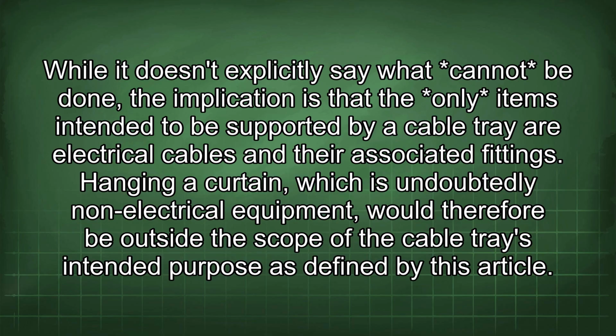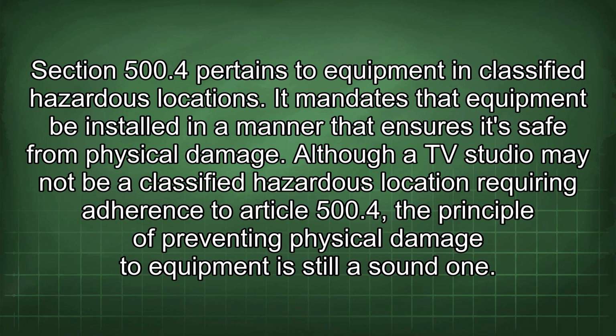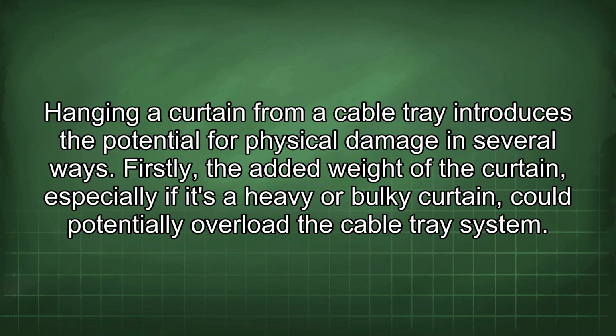Section 500.4 pertains to equipment in classified hazardous locations. It mandates that equipment be installed in a manner that ensures it's safe from physical damage. Although a TV studio may not be a classified hazardous location requiring adherence to Article 500.4, the principle of preventing physical damage to equipment is still a sound one. Hanging a curtain from a cable tray introduces the potential for physical damage in several ways.